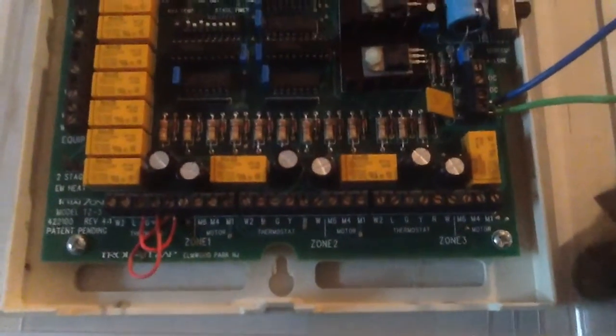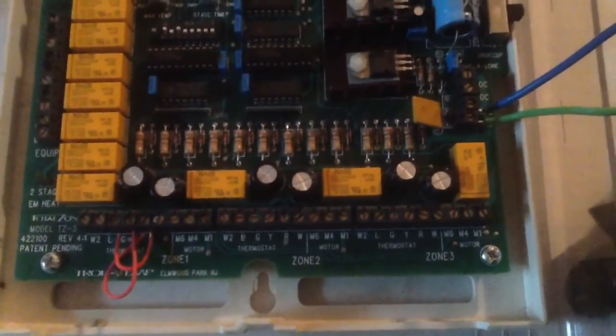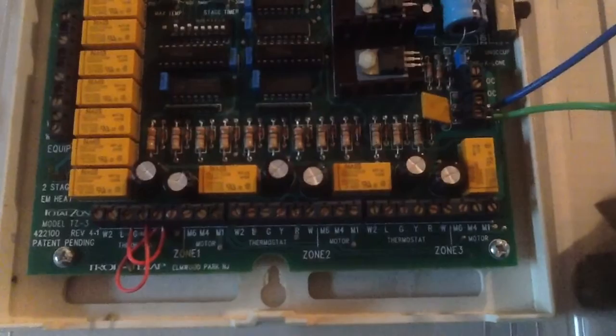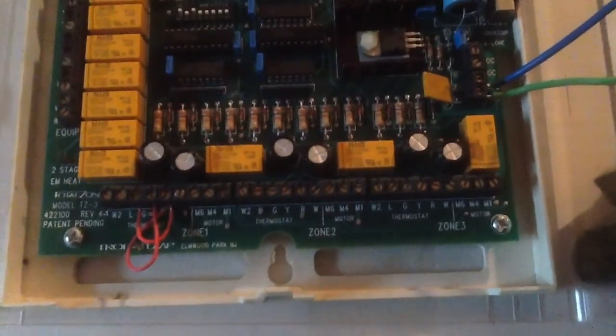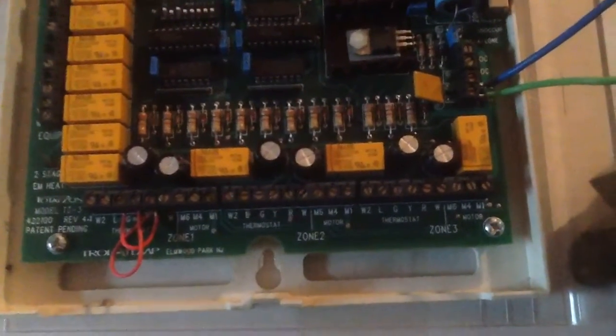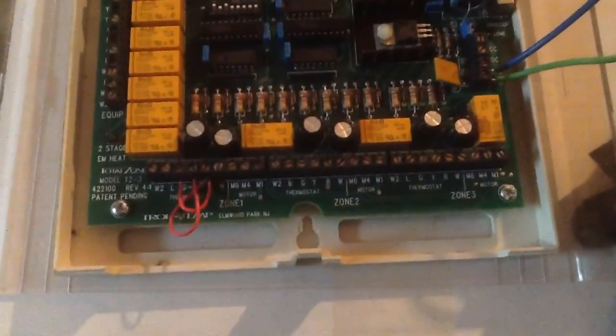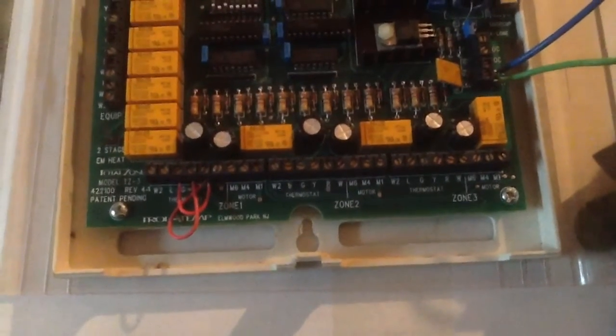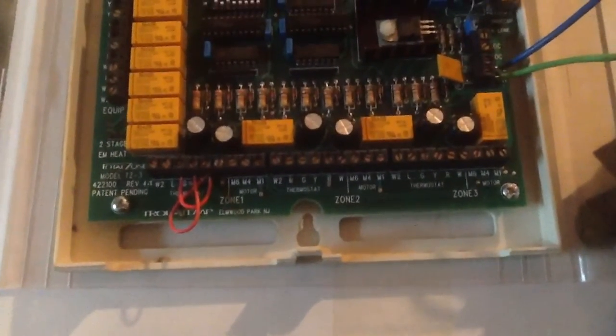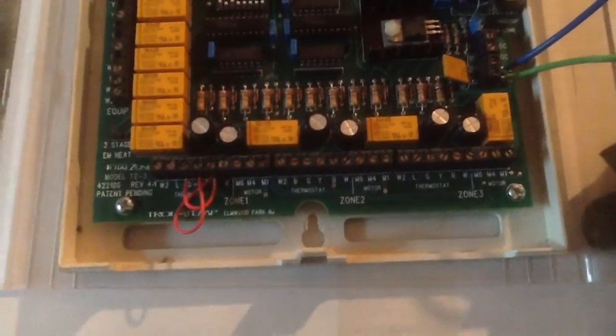And then the same thing goes over here. You got zone 2 thermostat and motor. So that's where your zone 2 thermostat would wire up, and your zone 2 damper would wire up there as well. Same thing goes for zone 3. So this board can handle 3 zones. So here's where you would run all your thermostat wiring and the appropriate damper motor wires to those zones here.